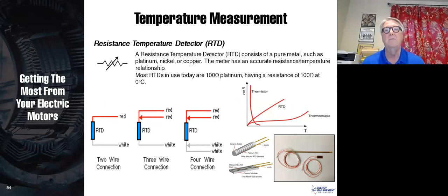So I did some investigation and found out that indeed they had wired them with only two wires. We were measuring the resistance of the wire and thinking that was the resistance of the RTD. And so they showed much hotter temperatures than was actually the case. So what we did was we actually had to buy some new temperature monitors. Didn't buy them new, we had them modified, and used 3 wires.